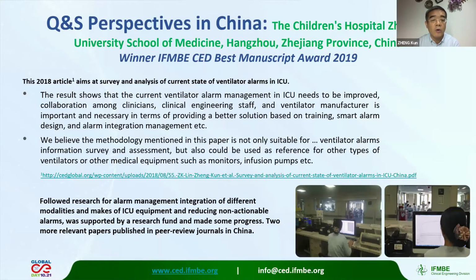For example, as the slide shows, as a winner of the IFMBE CED Best Manuscript Award 2019, the paper addressed the alarm management project in my facility. Based on the survey and analysis of medical equipment alarm situation in ICUs at the hospital, several measures to reduce non-actionable alarms and address alarm fatigue were implemented. This is even more important and needed in fighting COVID-19.